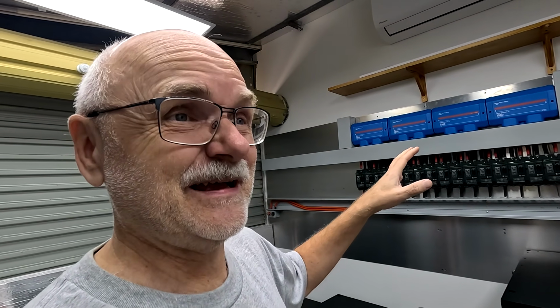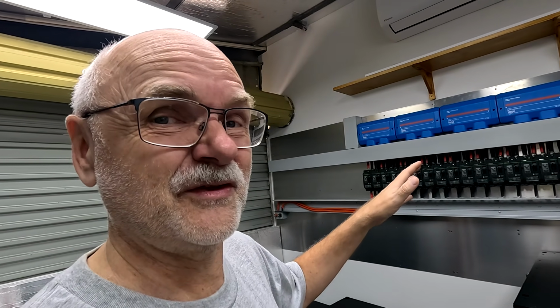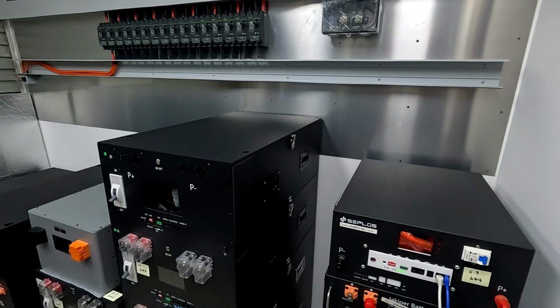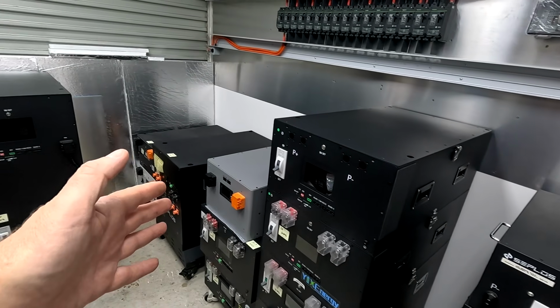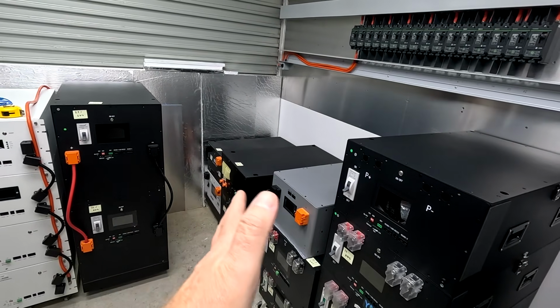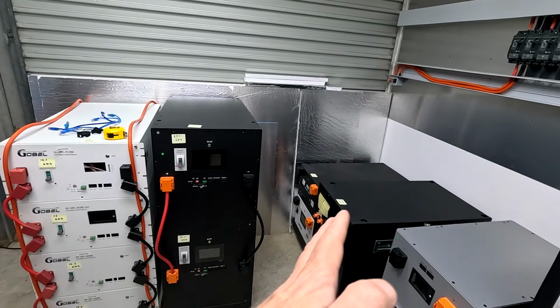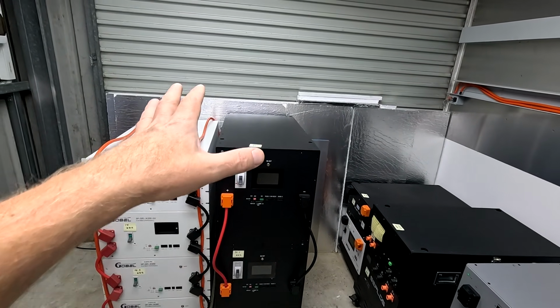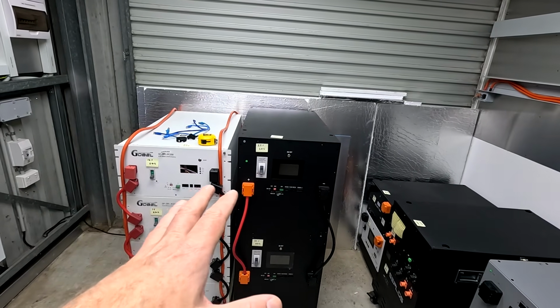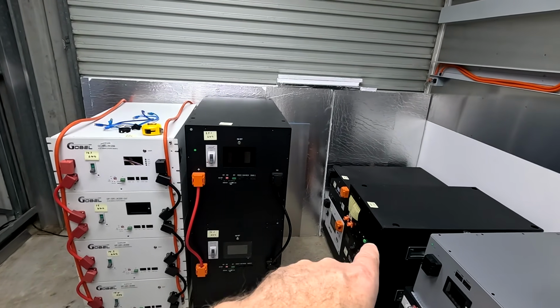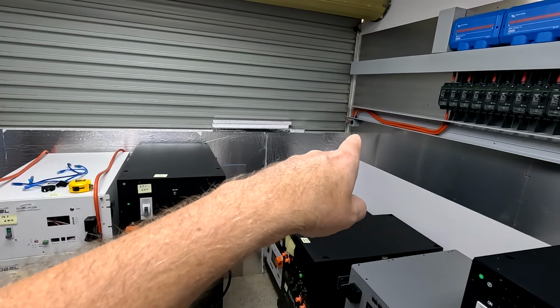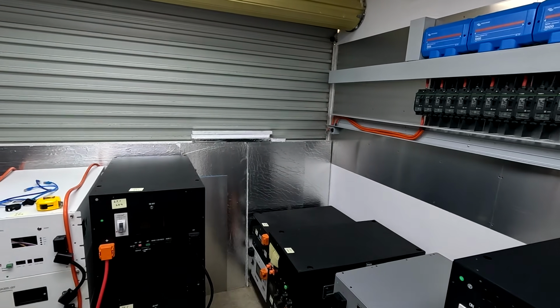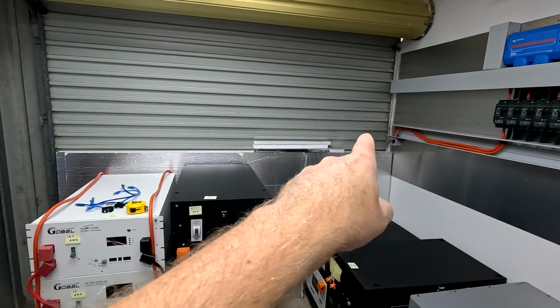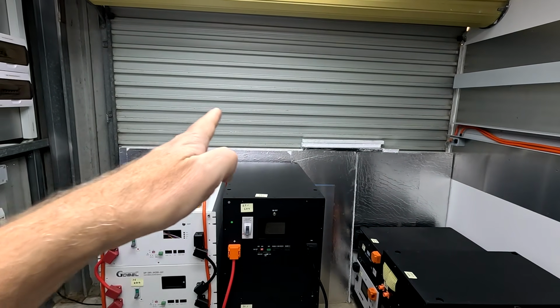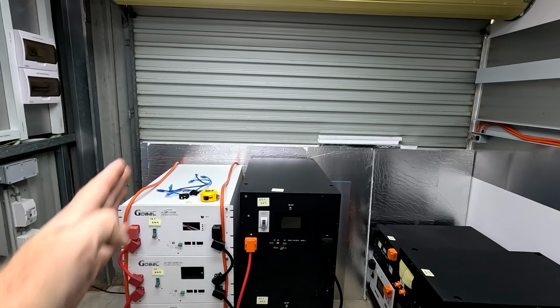While this is the extension part of the battery shelf, I am already working on an extension for the extension, because I did the battery fitting here. I've got all the towers, all the batteries sitting in the battery room now, and was looking at how everything fits. Some of the batteries are sitting on this side, against the roller door basically. I didn't like the idea of having the connection cables just running on the floor somewhere and then coming up to connect to the connection point over there. So I thought, why not extend this cable duct across the whole length of the roller door and give us more connection points for batteries on this side.